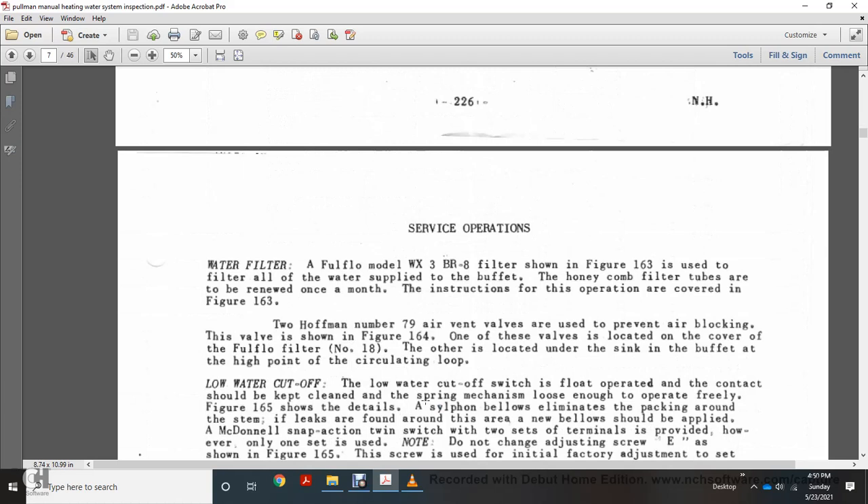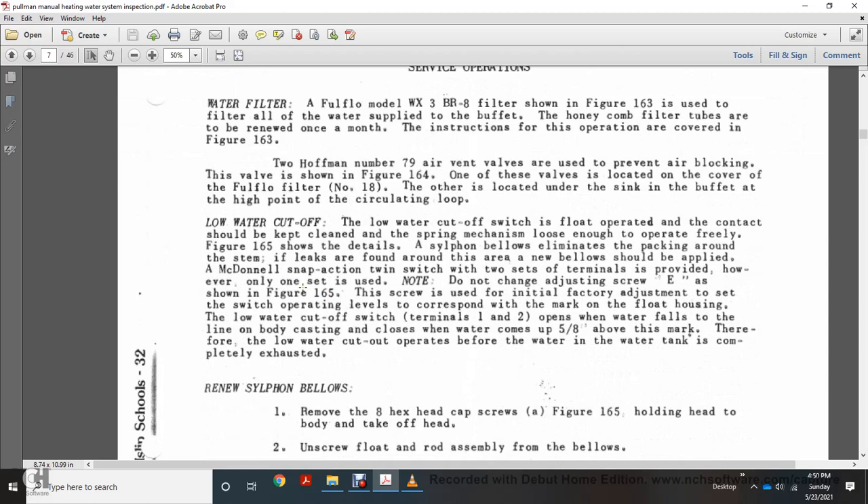The water filter is a Fulflo model WX3 BR-8 filter, shown in figure 163, which filters all water supplied to the buffet. The honeycomb filter tubes should be renewed once a month. The Hoffman number 79 air vent valve, shown in figure 164, is located at the high point of the circulating loop. The low water cutoff switch, shown in figure 165, has a float operating with contacts that should be kept clean and the spring mechanism loose enough to operate freely. The initial factory adjustment sets the switch operating level. When water falls to the limit line of the body casting, the cutoff operates before the water in the tank is completely exhausted — the cutoff operates when water is five-eighths of an inch above the mark.